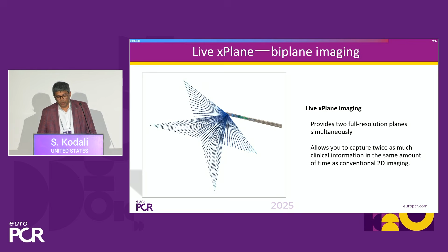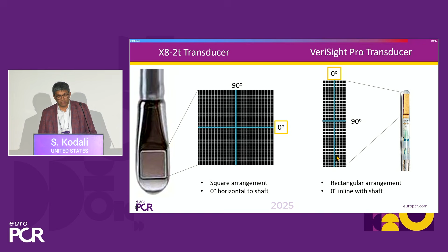But there are some limitations, and it's important to understand the differences. When you talk about TEE, it's a square phased array. Here, it's not. So in the 0 degree, it's not horizontal, it's vertical along the length of the rectangle, and the 90 is opposite. That has some important things we have to keep in mind, which both Matt and Gagan are going to show in their clinical cases. It limits, so the 90-degree field is not going to have the best quality imaging.